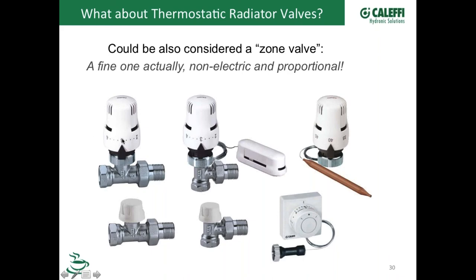So if you have a three position here, let's say that's maybe 68 degrees is where that valve is set, it'll just modulate that disc in there so that you're just getting the exact temperature that that valve is set at. Now you don't have to wire it back to a thermostat, to a relay box, or anything like that. It can be put right out on the heat emitter, on the panel radiator, on a cast iron radiator, different jobs. We do have some with remote sensors.